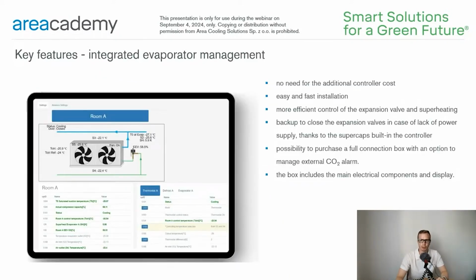The third key feature is the integrated evaporator management. Depending on the iCool CO2 model, our multifunction unit controller can manage up to 2 additional expansion valves. In certain cases, the whole installation may be controlled through our built-in controller. Thanks to this, there is no need for the additional controller cost. The installation startup can be easier and faster. The control of the expansion valve and superheating is more efficient.